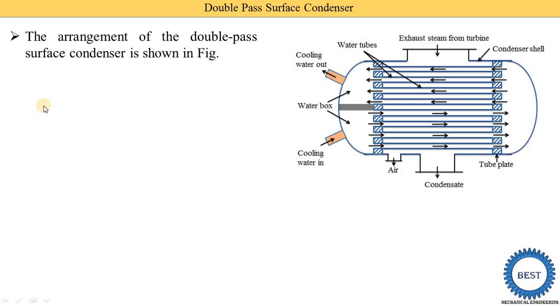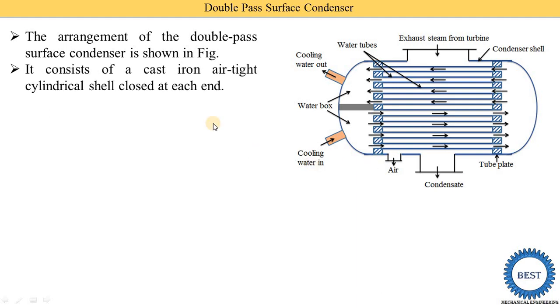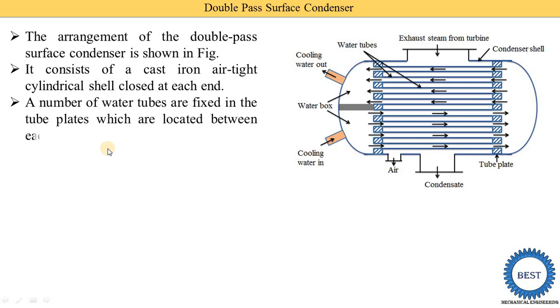The arrangement of the double pass surface condenser is shown in this figure. This heat exchanger consists of cast iron — an airtight cylindrical shell closed at each end by heads installed on both ends. A number of water tubes are fixed in the tube plates which are located between each cover head and the shell. In the front view we see only seven to eight tubes, but from the side view there are many more tubes.